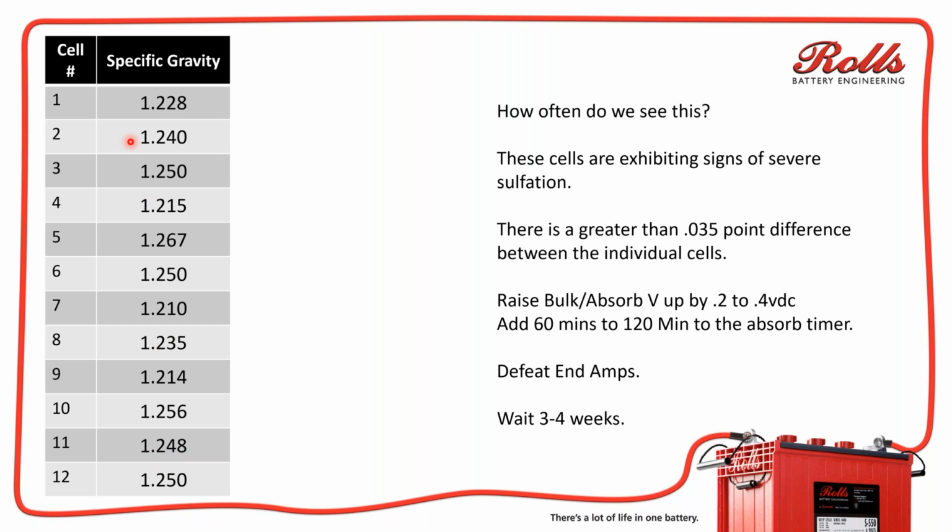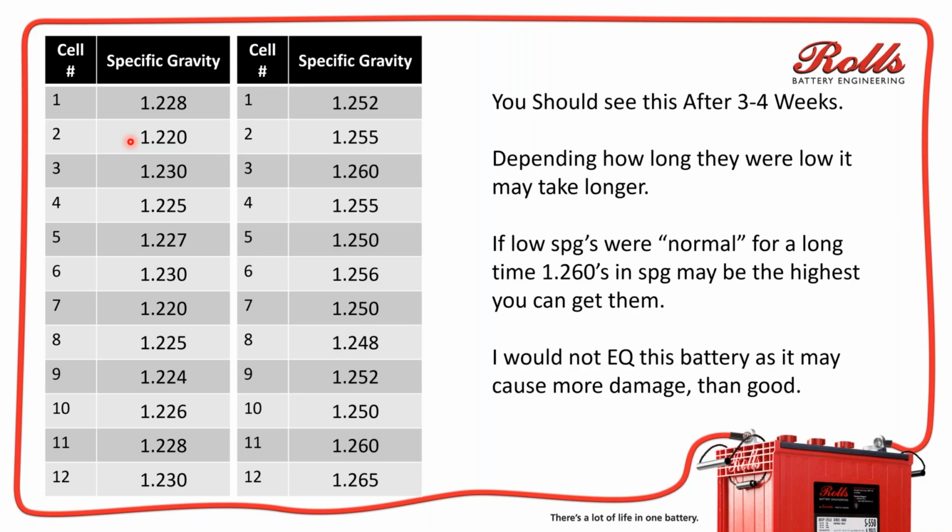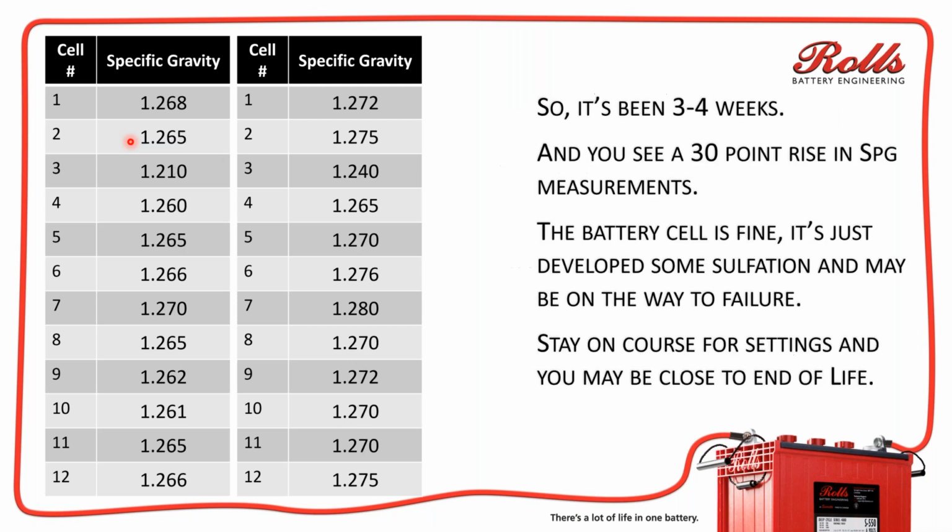There can be cases where you see them all relatively close, like for example this one here, where all the specific gravities are relatively close. The batteries are basically just being undercharged here, okay?